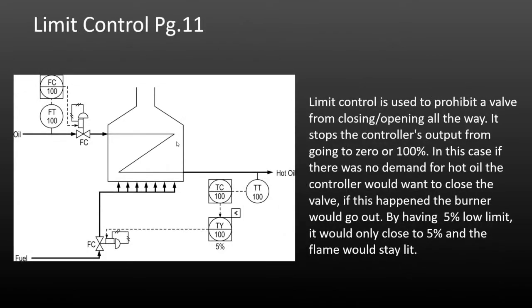Here's a limit control application — a furnace fuel gas example. With most furnaces, like furnaces in our homes, we have pilot lights that stay on all the time. Industrial furnaces are similar — we need a minimum amount of fuel required in order to keep the furnace burning. Limit control is used to prohibit a valve from closing or opening all the way, stopping the controller from going to zero or 100% based on whatever setting we put into it.